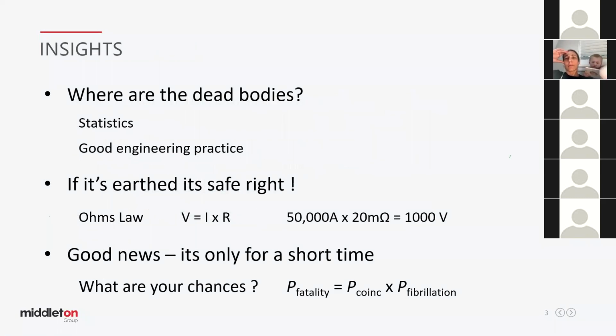So a few insights. Where are the dead bodies? That's, I guess, the question that people would like to know the answer to. That's what drew you to this seminar. Well, statistically, I'm not aware of any dead bodies, that is electrocutions, attributed to a voltage that's been created on a conductive surface by an earth fault. So we're not talking about direct contact with high voltage conductors here. We're talking about voltages that are created due to an earth fault, say in a switchyard or a substation out in the street.